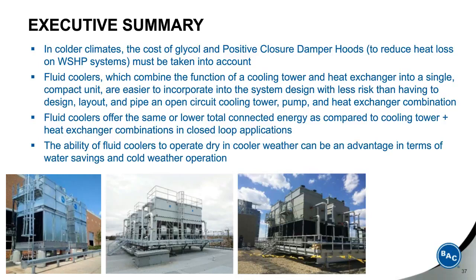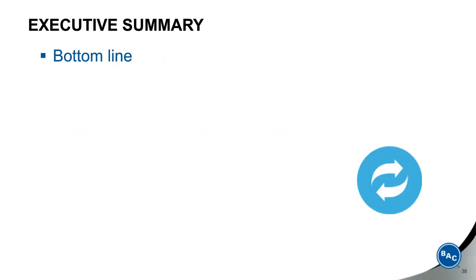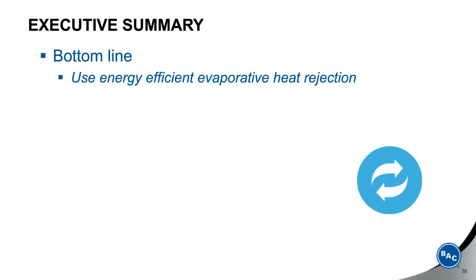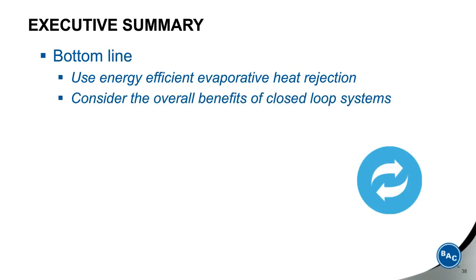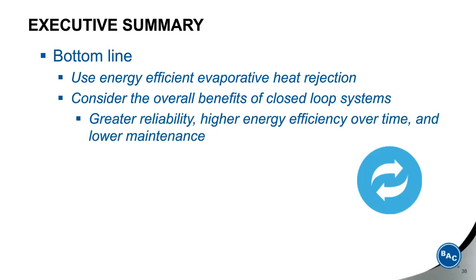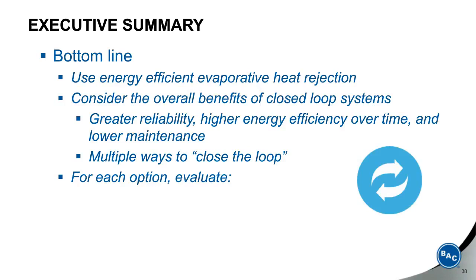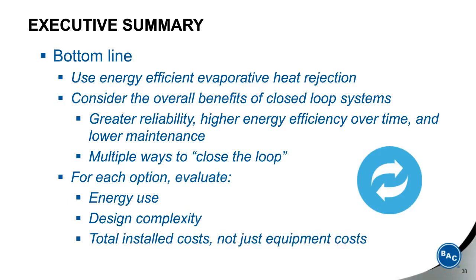So, having made those summary statements, what is the overall conclusion here? What's the bottom line? Use energy-efficient evaporative heat rejection when it's appropriate. Consider the overall benefits of closed-loop systems versus open systems, when that might be the higher or greater reliability, higher energy efficiency over time, and lower maintenance. And there are multiple ways you can achieve closing the loop. For each option, make sure that you evaluate the total energy use, the design complexity, the total install costs, not just the equipment costs, and then the impact of the climate zone you're intending to put the unit into.